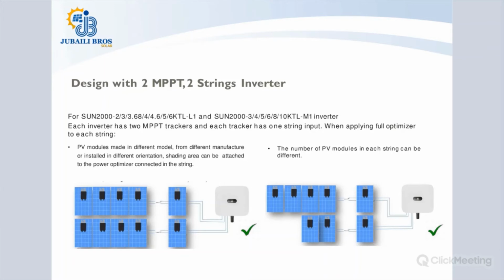Now let's take a look at designing with PV optimizers. Here we are taking a look at the single phase optimizers from Huawei, the 2 to 6 kilowatt inverters from Huawei. These inverters have 2 MPPTs, and each MPPT has 1 string input. So it has 2 MPPTs and 2 strings. Now remember, we said with the simple system, the maximum DC power that we can have in a string is what? Is 5 kilowatts. So these 2 MPPTs are independent MPPTs.